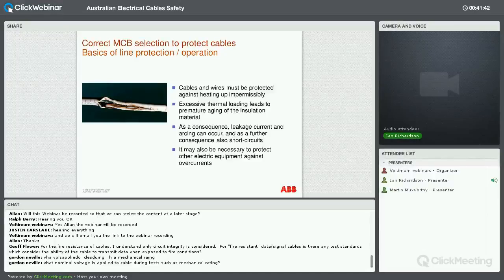Why do we need to do it? Well, essentially, in a very simple view, you can see there's a small, pretty much a flexible cable here, which has been affected by heat. Obviously as cables carry more current, there'll be more heat generated, and depending on the cable, that can have an effect on the integrity of the cable, and we can get quite severe breakdowns if we don't do something about that.